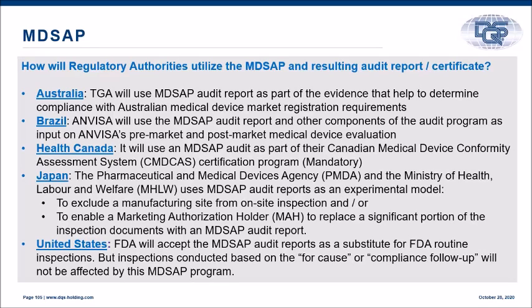Brazil, same. ANVISA will use the MDSAP audit report and other components of the audit program as input on pre-market and post-market medical device evaluations. So Brazil is a big beneficiary of the MDSAP program. The reason is they had a long list of pending ANVISA inspections or audits to be completed. Once this came up and they became part of it, that's a big relief for them in terms of clearing up that queue, and many manufacturers have also benefited from this.